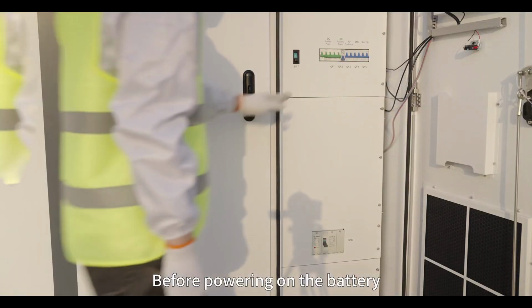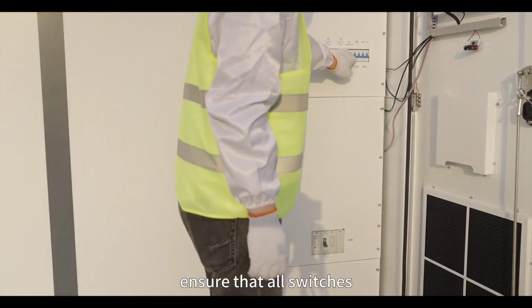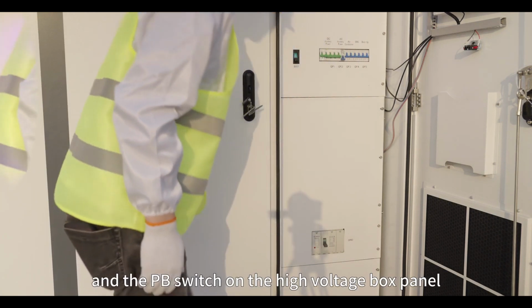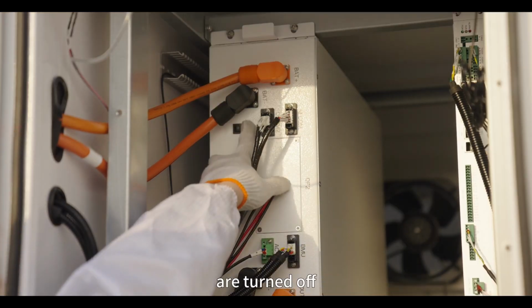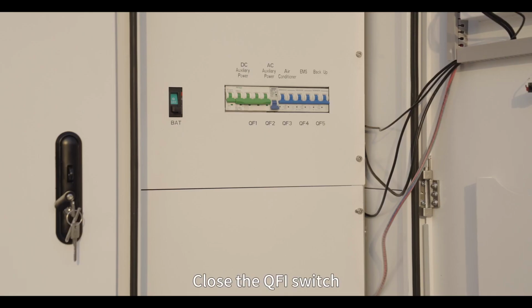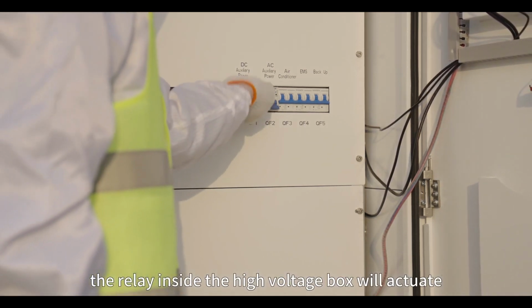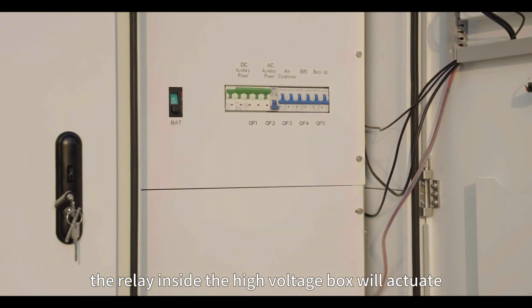Before powering on the battery, ensure that all switches, circuit breakers, and the PB switch on the high voltage box panel are turned off. Close the QF1 switch. The relay inside the high voltage box will actuate.